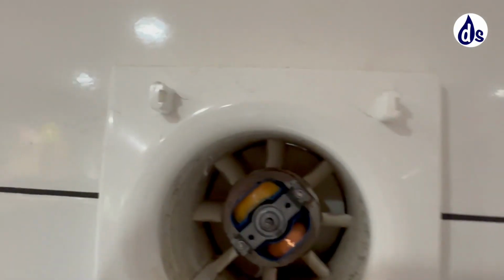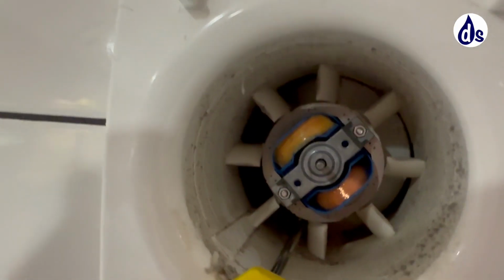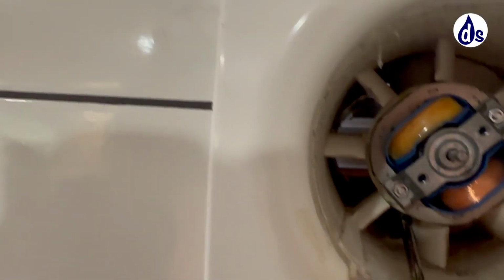Fantastic. So there's nothing majorly wrong. There's what are called backflow shutters, which I don't particularly like, and given that it's already got flaps to stop the air blowing it back in, it seems pointless. The top things shouldn't really be there, but in my experience they don't make a huge difference. I just wonder whether it's not working very well, a bit old. I'll do a bit of a clean up and see if we can improve it.